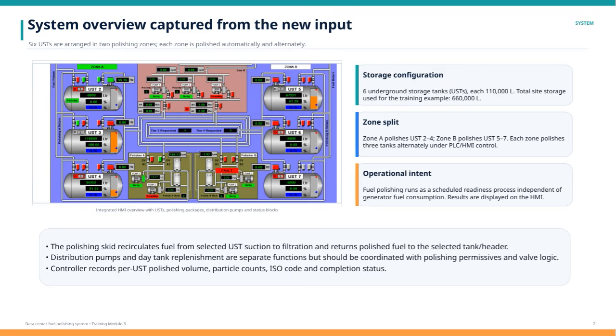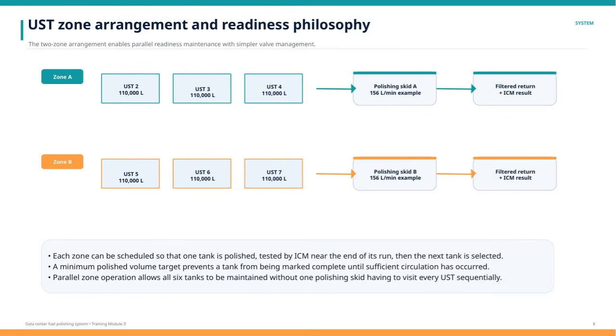This setup is part of the Data Center Fuel Polishing System Training Module 3. Here we see the UST zone arrangement and its readiness philosophy. The system is divided into 2 zones, Zone A and Zone B, each with 3 underground storage tanks of 110,000 liters capacity. This 2-zone setup allows us to maintain readiness in parallel, simplifying valve management and operation.